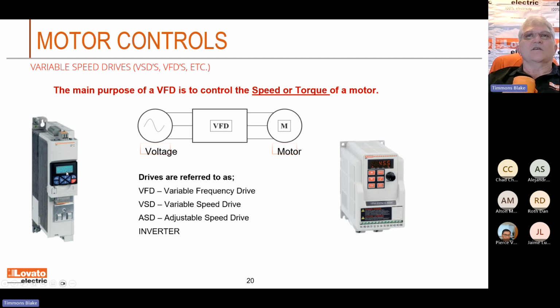VFDs, I'm not going to get too deep into VFDs. That's pretty much a class on its own. But I just want to say that the main purpose of a VFD is to control the speed or the torque of a motor, not just for starting it up. Really, a VFD is a better control of things if you need that. Soft starters work good just to help reduce the mechanical shock and the peak surge on the voltage. But the VFD gives you a lot of control, and it has different names. People call it variable frequency drive.